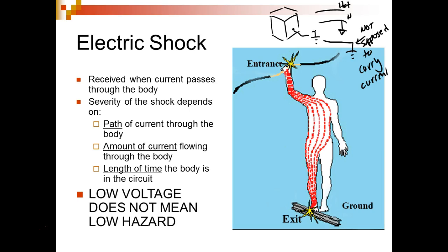Well, what had happened is my grandmother's son came in there and used an extension cord to power up a refrigerator because it wasn't by a plug. He cut the ground off the plug because it was a 2-wire plug instead of a 3-wire extension cord, and he plugged it in backwards. That meant the chassis that came into contact with the metal was now connected to the hot, and the hot was connected there. We left off the ground, so he had no ground. Even though he wired it backwards by plugging it in backwards, he made the chassis hot, you understand?